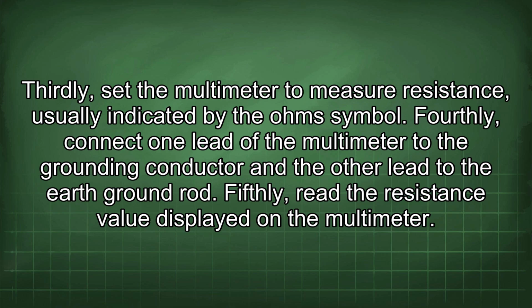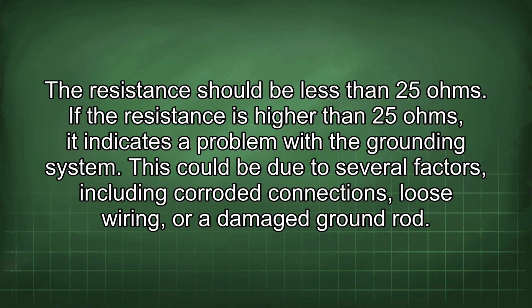Thirdly, set the multimeter to measure resistance, usually indicated by the ohm symbol. Fourthly, connect one lead of the multimeter to the grounding conductor and the other lead to the earth ground rod. Fifthly, read the resistance value displayed on the multimeter. The resistance should be less than 25 ohms. If the resistance is higher than 25 ohms, it indicates a problem with the grounding system.